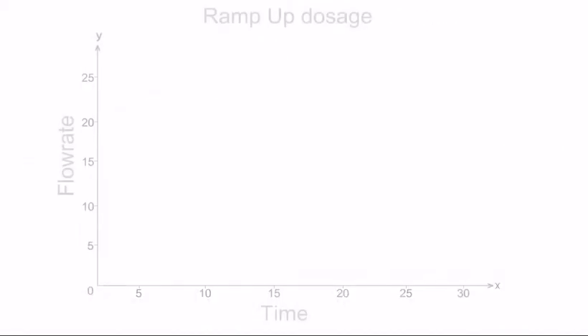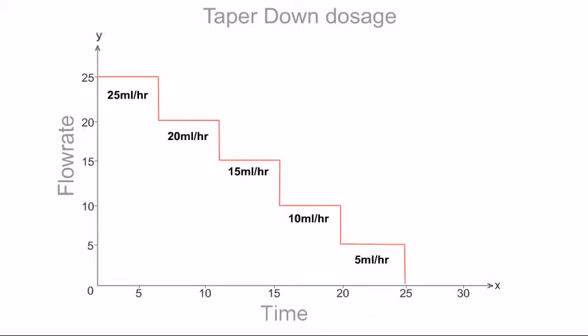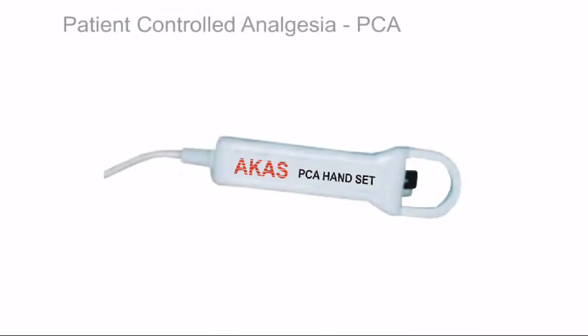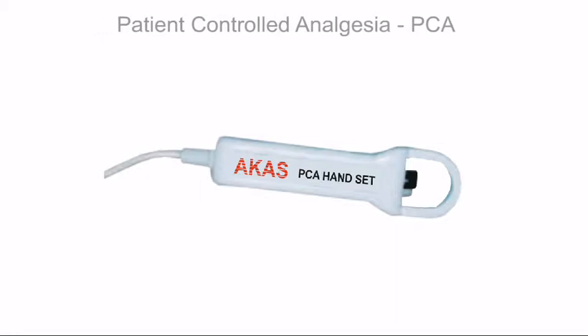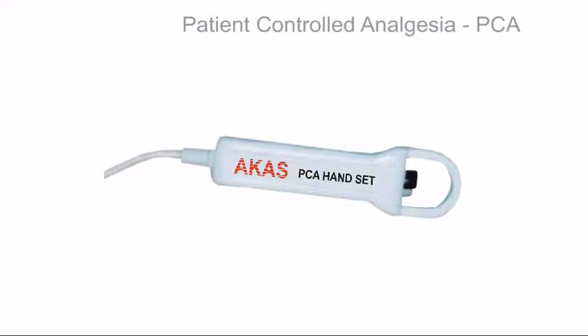Ramping up or tapering down dosage in five different steps of flow rate and time duration is possible, thereby user intervention for changing parameters is not required at every stage. Patient Controlled Analgesia, shortly called PCA, is an optional attachment at economical cost. PCA has a programmable lockout time interval between two bolus activations; however, the patient hears the activation to give a psychological feel of analgesic drug delivery.